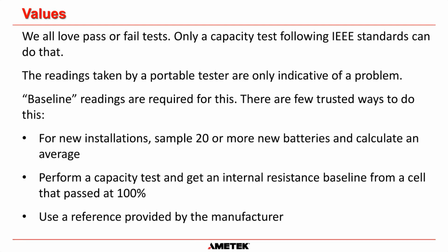And we need to have baseline readings to be able to analyze what's going on with these readings. And there are a few trusted ways to do this. And what I mean by a baseline reading is a reading that you can refer to and compare the measurement that you have just taken. And if it increases for resistance, then you know there's a problem. Or if it decreases for conductance, you know that there is a problem.